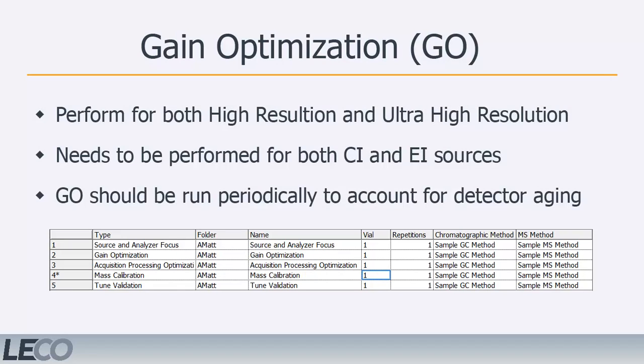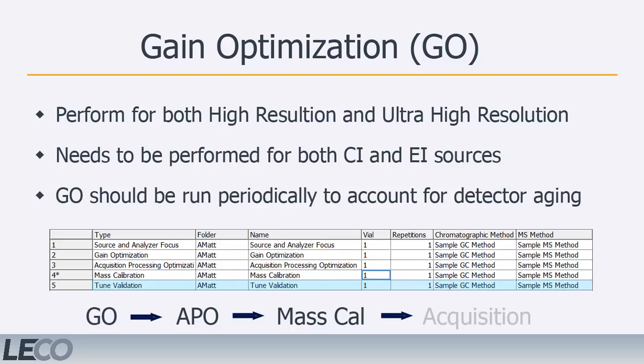The gain optimization will need to be performed in high resolution and ultra high resolution modes for both electron impact and chemical ionization methods. The gain optimization does not need to be run daily, but needs to be rerun from time to time as the detector ages. Once the gain optimization has finished, acquisition processing optimization and mass calibration steps must be run before continuing to sample acquisition.